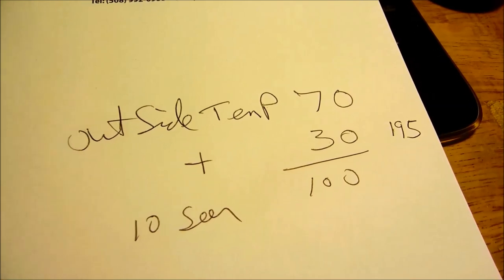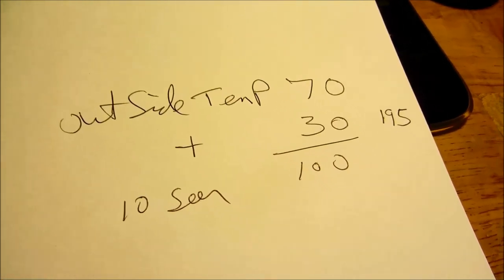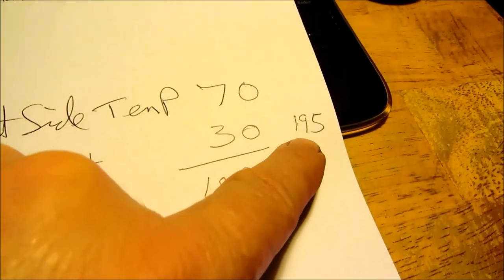Then you go over to PSI, it's 195. So the head pressure on a 70 degree day on a 10 SEER unit should be more or less 195.